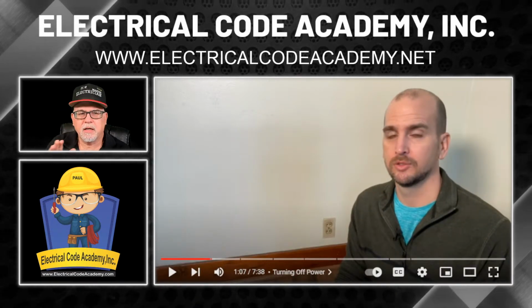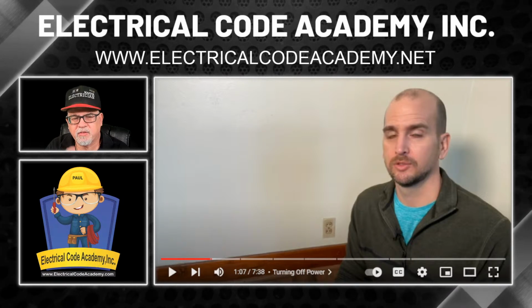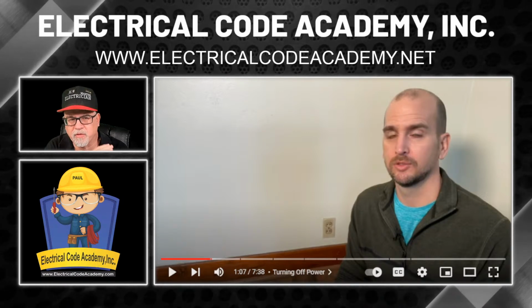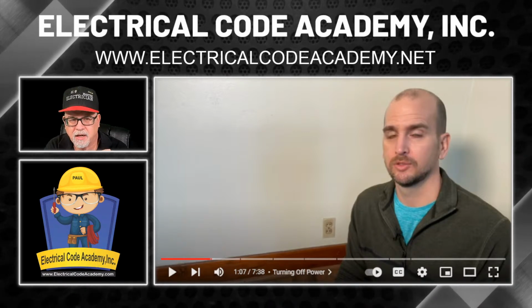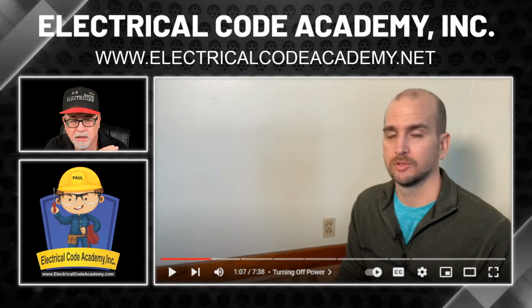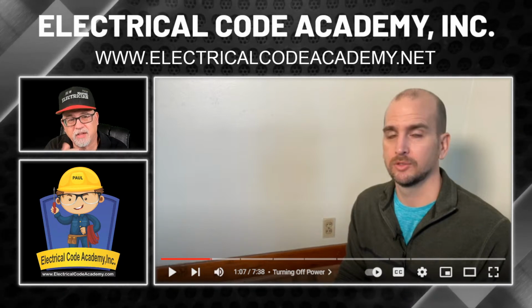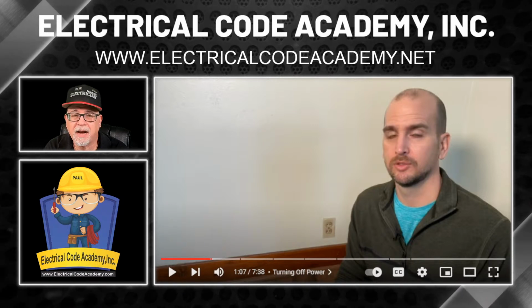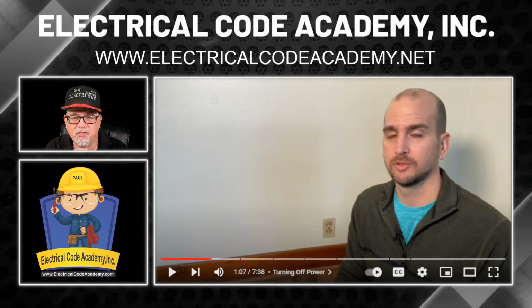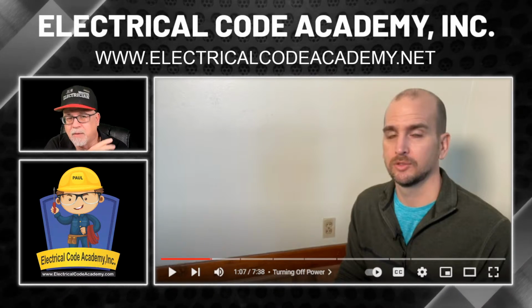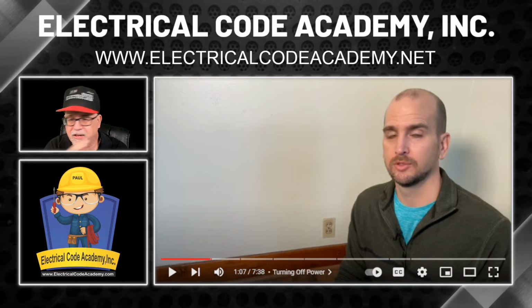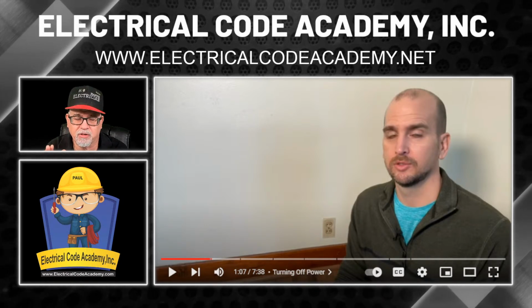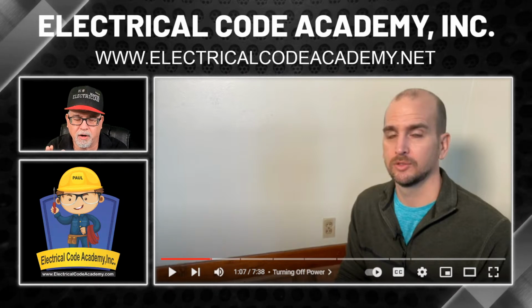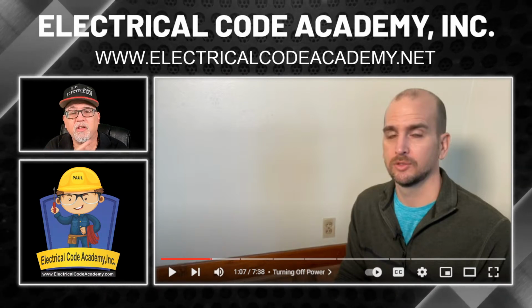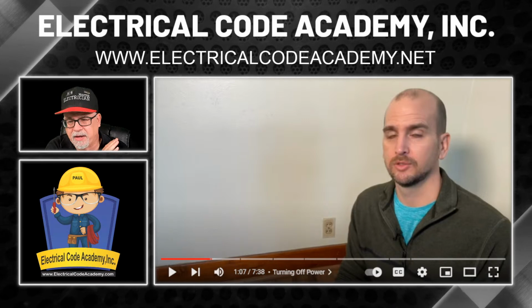Now remember, there's also the ability, let's say this is an older house and there was a service upgrade or a service change. If the panel is newer, but the branch circuits are existing and it's older, then you might have the option to put a GFCI circuit breaker in the panel, and it protects everything downstream and achieve this goal of being able to change out all these receptacles to 3-prong instead of 2-prong. Okay, so there are other options, but that only works if you have a panel that can accept it.